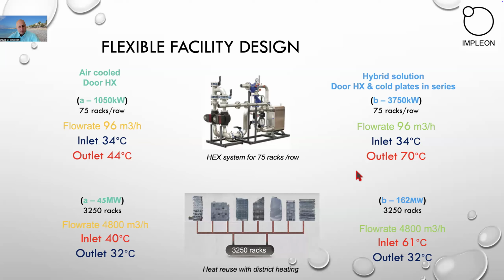In that case, it's important to have a flexible design, where we can start with only air-cooled racks with 1 megawatt for 75 racks with this flow rate and these temperatures. After that, we shift to liquid cooling and have 3.7 megawatts, but the same flow rate. And this we achieve with on-chip cooling. And the same on facility level, so we can have 45 megawatts with this flow rate. And we can achieve 162 with the same flow rate by playing with the temperatures.